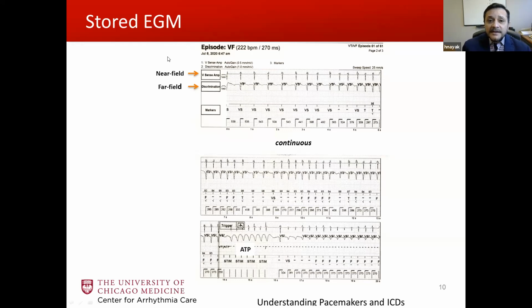And so once again, a near field, far field electrogram. So what do we mean by near field? The near field electrogram for an ICD is, what is the ICD lead seeing? A near field electrogram is generated when a wave of depolarization is heading towards the tip of the ICD lead, and it's basically seeing between tip and ring, giving you a very narrow focus or view of what's going on. The far field electrogram is generated when that wave of depolarization hits the ICD lead, and it's recorded between the tip of the ICD lead and generally the distal coil. It gives you a broader view of what the device is seeing. And the markers sort of tell you what the device is interpreting and looking at.